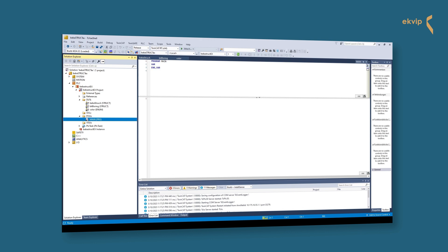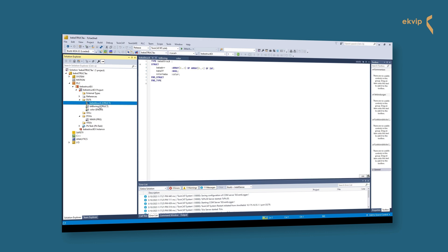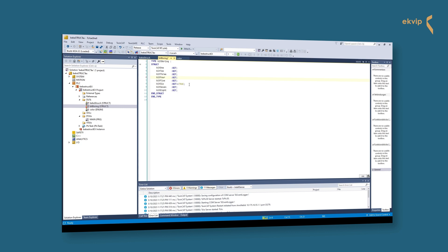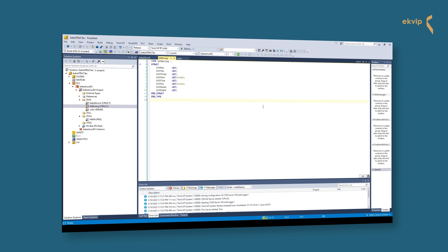Now we want to show you some other basics. In the DUT section you can see that we prepared two structs. One is called a_bit_boring. In here we declared eight variables of the data type BIT. BIT is a boolean data type which can only be used within structures or function blocks — that's why we thought it would make sense to mention it here. It requires one bit of memory space. BIT elements which are declared sequentially are consolidated to bytes, allowing you to optimize memory usage compared to Bool types which each occupy at least eight bits. However, BIT access takes significantly longer.